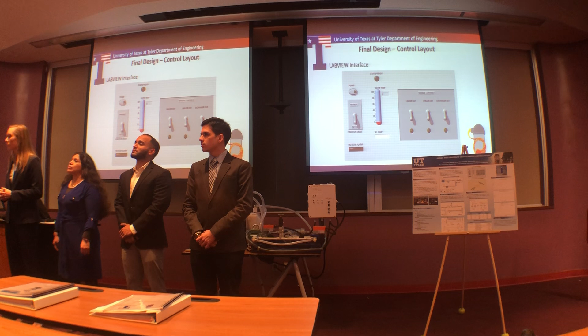When I say the logic behind it, I don't mean the reasoning behind it. I mean how you determine no flow. Oh, the flow meter. The flow meter gives out a current. So if the current is high, then there is flow. Right. But do you do any averaging, any time condition for no voltage, or if it just had an intermittent loss of signal, is it going to shut your system down? As soon as there's a loss of signal, that is the way it's currently set up.